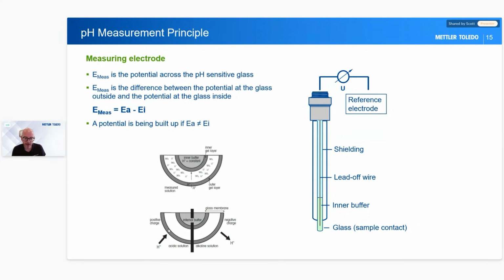If we have an acidic solution, those H+ ions flow in and cause a positive charge. If we're in an alkaline solution, they flow out into our solution and cause a negative charge. Once we've got this charge, this is our measuring charge. The really important thing with the measuring bulb is that the gel layer on the glass has to be absolutely clean. It has to be well adhered to the glass, and it has to be full of H+ ions ready. If it is broken away from the glass, or doesn't have the H+ ions ready to go, it's not going to work.